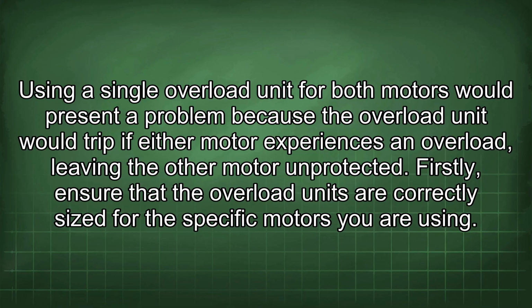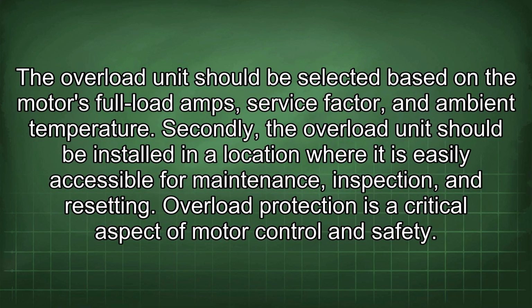Firstly, ensure that the overload units are correctly sized for the specific motors you are using. The overload unit should be selected based on the motor's full load amps, service factor, and ambient temperature. Secondly, the overload unit should be installed in a location where it is easily accessible for maintenance, inspection, and resetting.